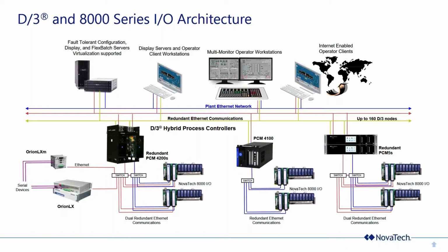If it cannot talk to PCM A over either of its networks, A or B, then it will switch to the backup EBIM. The backup EBIM, which now becomes the master, will talk to PCM A over the A network. If it can't talk to it over the A network, it will talk over the B network.